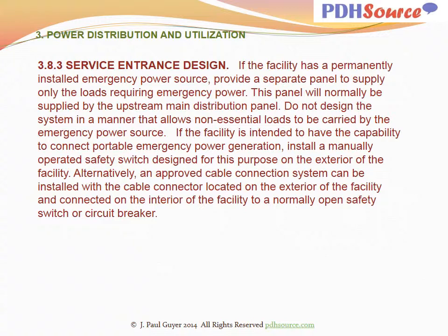If the facility has a permanently installed emergency power source, provide a separate panel to supply only the loads requiring emergency power. This panel will normally be supplied by the upstream main distribution panel. Do not design the system in a manner that allows non-essential loads to be carried by the emergency power source.